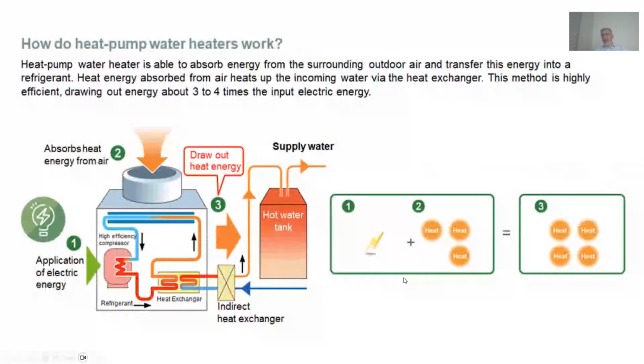Why do we say the COP is the best compared to other solutions? What is happening in a CO2 application? You use 1 unit of electricity and extract 3 units of heat from the environment, and the result is 4 units that can be used for heating purposes. That's why we say it's a COP of 4. We put 1 unit of energy in to run the machine, extract 3 units from outside, and provide 4 units in total to produce hot water.